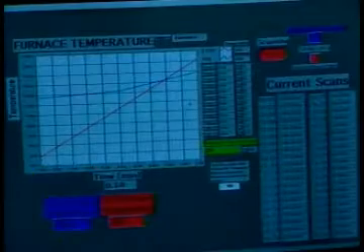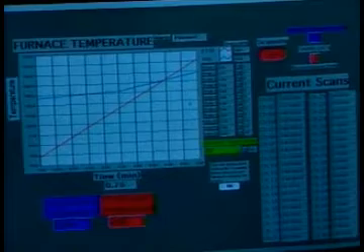Now the ASTM E119 test is repeated on fiber-reinforced gypsum panels. Gypsum can be retested for 1 hour, and if it passes the hose stream test in that 1 hour, they give it a 2-hour rated assembly. Unfortunately, that doesn't really reflect what happens out in a fire condition. You know, we don't get a second chance in fires.